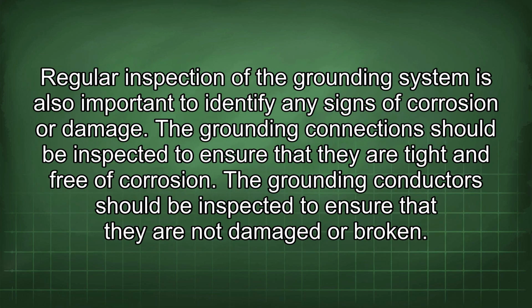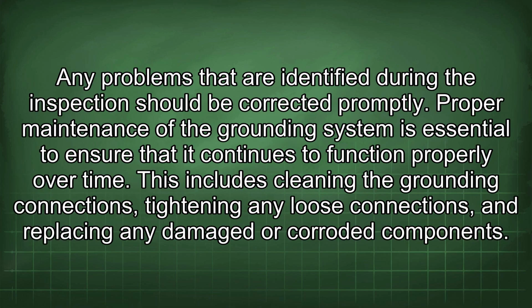Regular inspection of the grounding system is also important to identify any signs of corrosion or damage. The grounding connections should be inspected to ensure that they are tight and free of corrosion. The grounding conductors should be inspected to ensure that they are not damaged or broken. Any problems that are identified during the inspection should be corrected promptly.